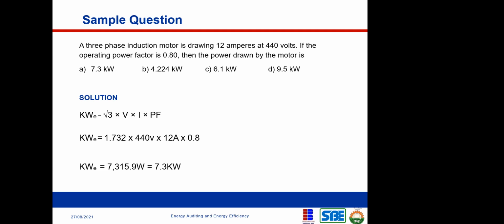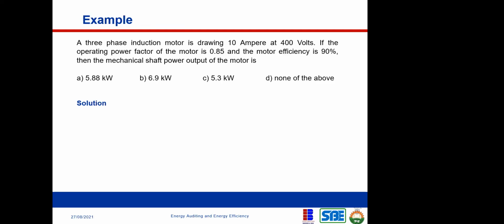It's simple and straightforward. The kilowatt electrical, like I said, first of all, we know it's a three-phase motor, and we should keep in mind that if it's a three-phase motor, we must introduce this root here, then times our voltage times our current times power factor. This is a straightforward question. Once you plug in the known values, you get the kilowatt electrical, and it's 7.3 kilowatts. Let us look at another example. A three-phase induction motor is drawing 10 amperes at 400 volts. If the operating power factor of the motor...